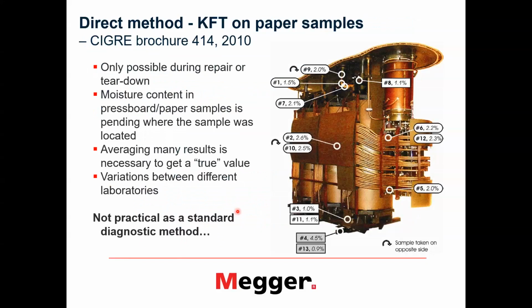Talking about the direct method, Karl-Fischer titration on paper samples, which is described in the CIGRE brochure. It is possible only if you open the transformer, go inside and grab a sample. It is also very difficult to get a representative sample from the transformer, since various locations may have different water contents. Like here, different samples were taken from places on top of the transformer, on the bottom, from the pressboard, from the windings, and you see there is a range from like 0.9% to 4.5%, and it depends on where you get the samples. So it is rather impractical to be used in the field as a diagnostic method.